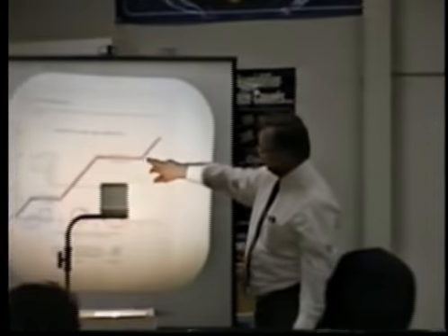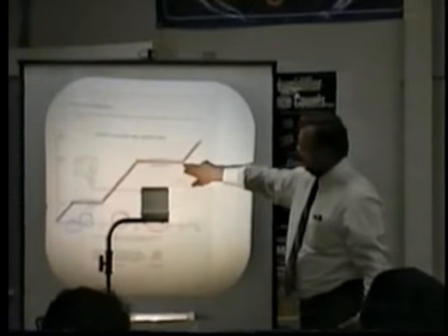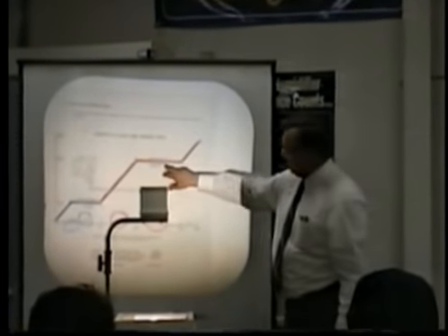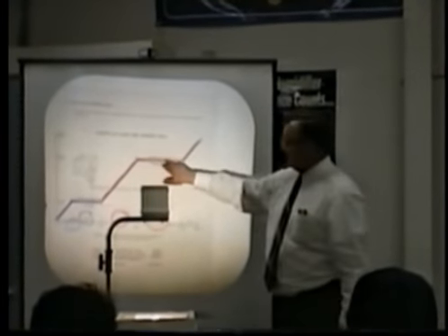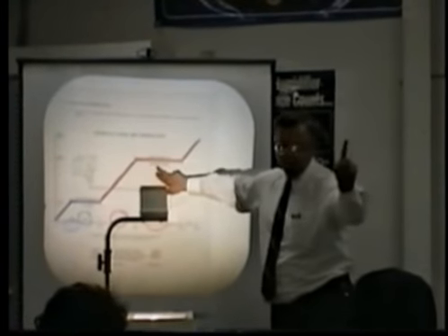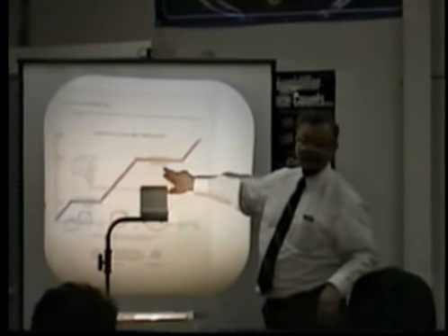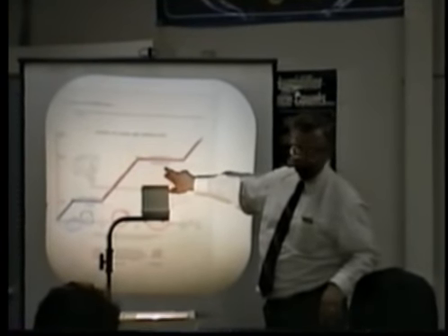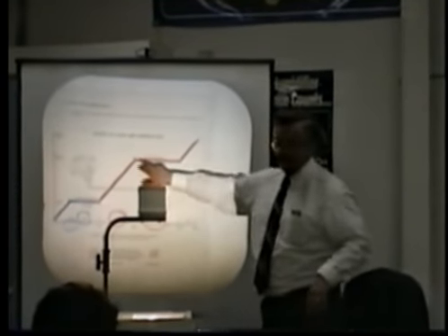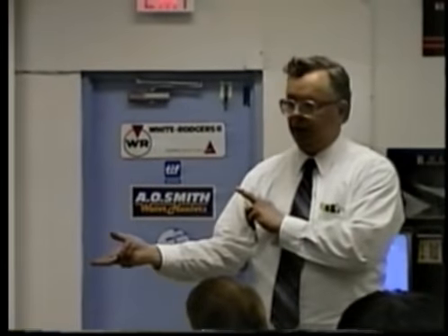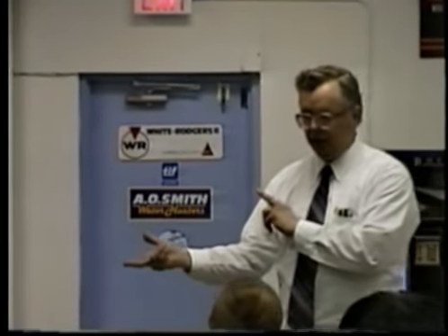Almost 1,000. So 970, right? If I remove, and it doesn't have to be steam, the word is vapor, if I can remove 970 BTUs per pound, I can end up with a pound of water. If we go this way, it's latent heat of vaporization. If I go this way and remove BTUs, it's latent heat of condensation. Now I'm condensing. I have vapor and condense it into water, or if I heat it up, I have water and evaporate it into vapor. Is that clear? You gotta know that.